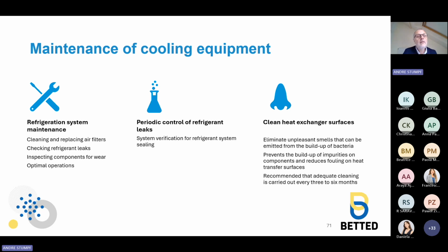Okay, just a few words about maintenance of cooling equipment. So we have three parts. The refrigeration system maintenance, first of all. One of the most important aspects of refrigeration management is regular maintenance of the refrigeration system. This includes cleaning and replacing air filters, checking for refrigerant leaks, and inspecting components for wear. Regular maintenance ensures that the system is running at its optimal performance level and reduces the risk of breakdowns and repairs. So, periodic control of refrigerant leaks.